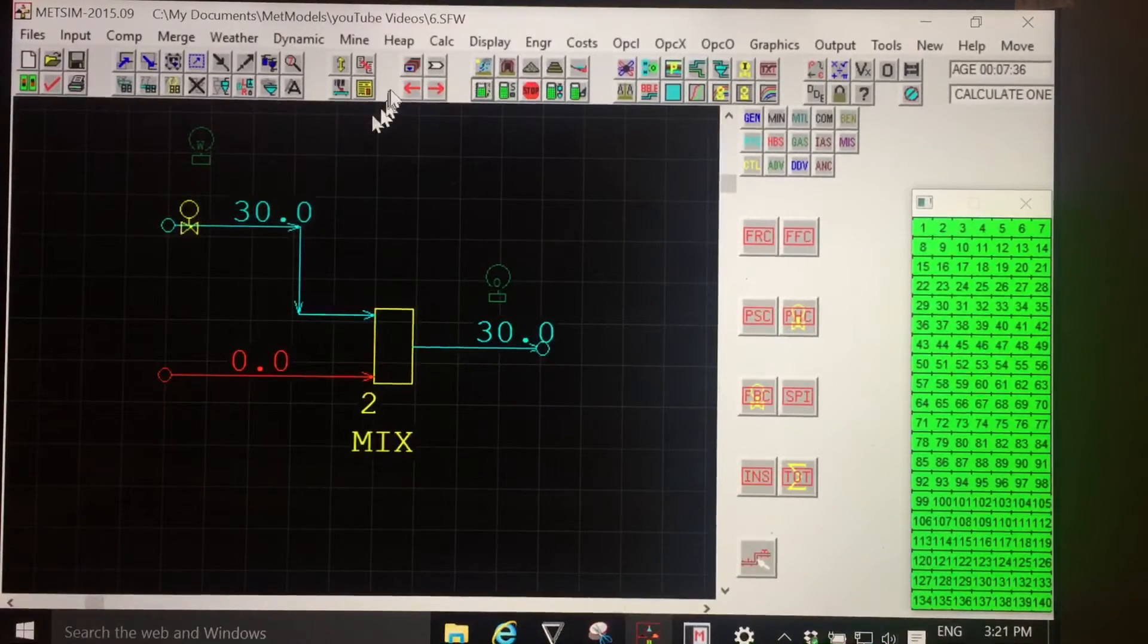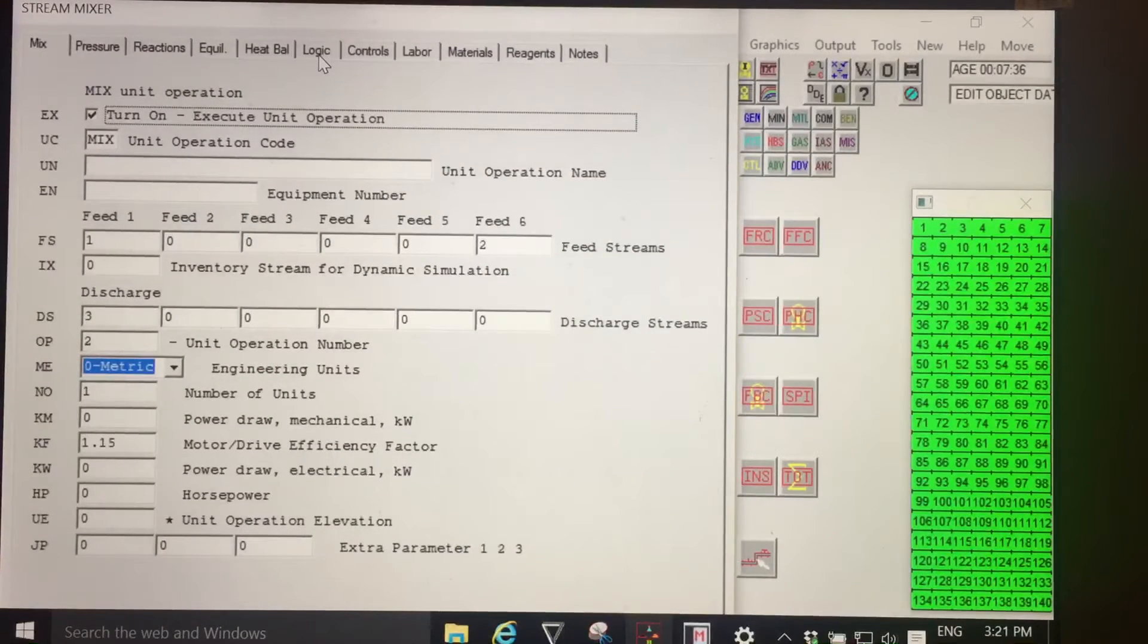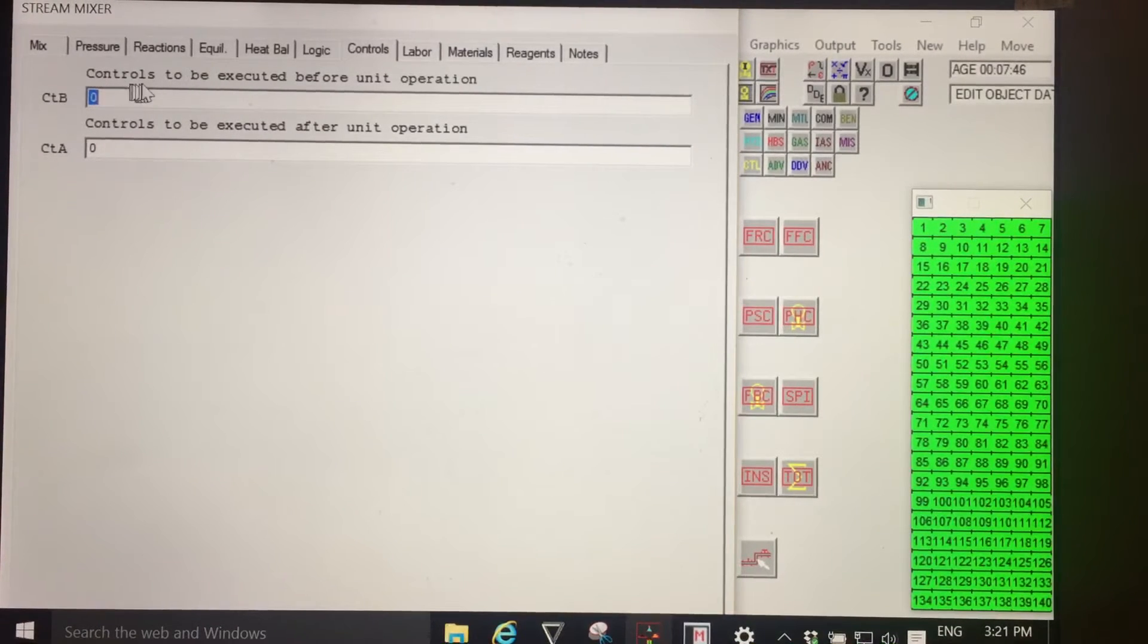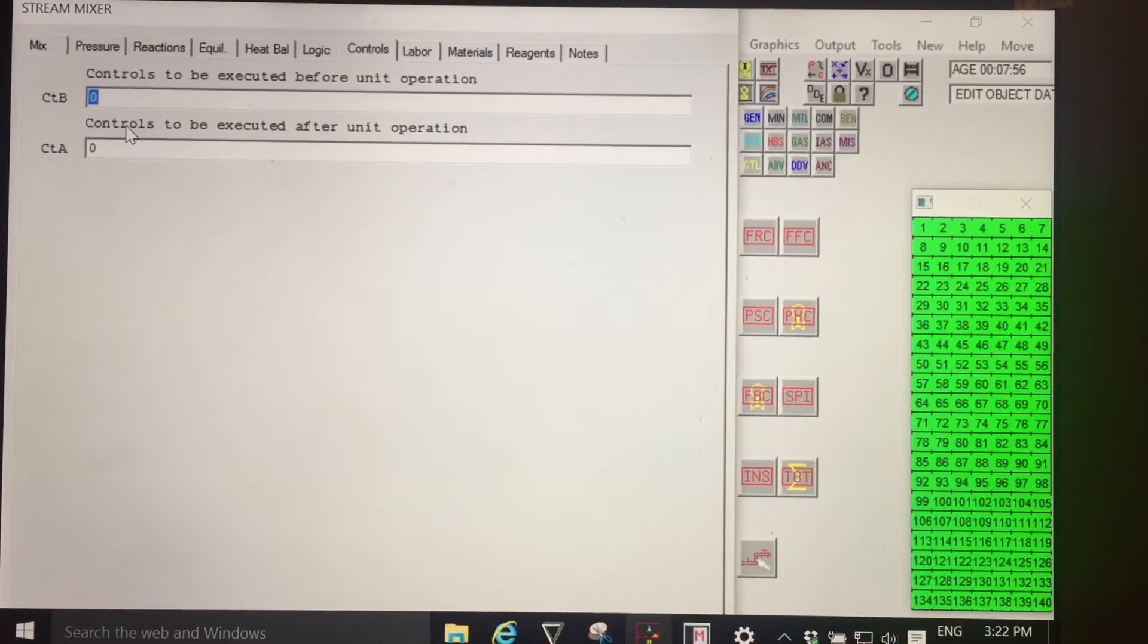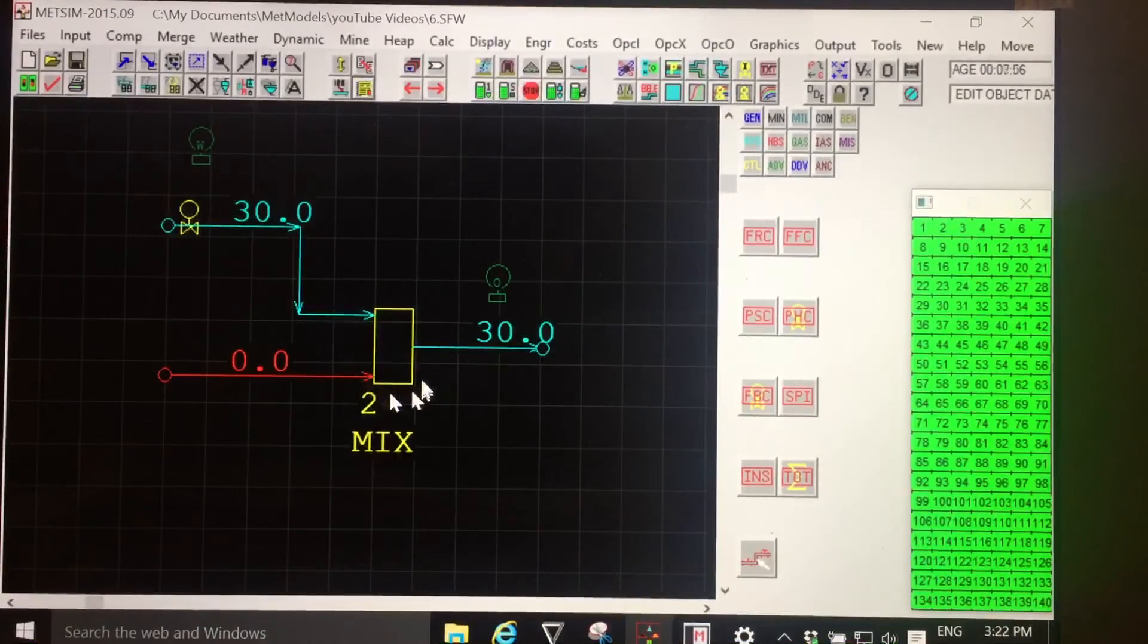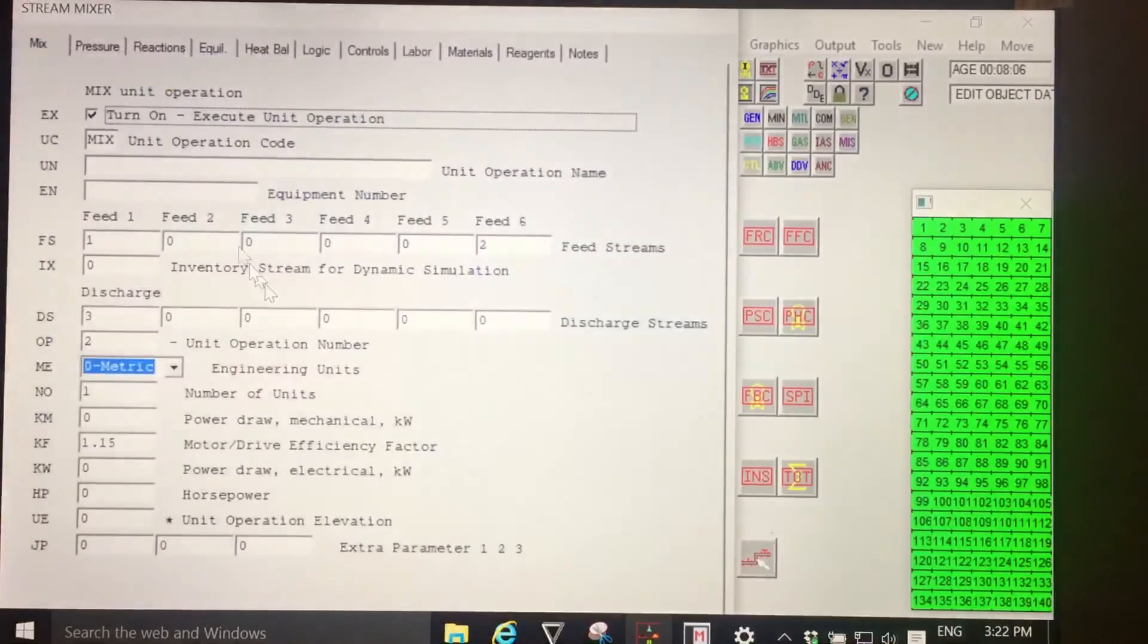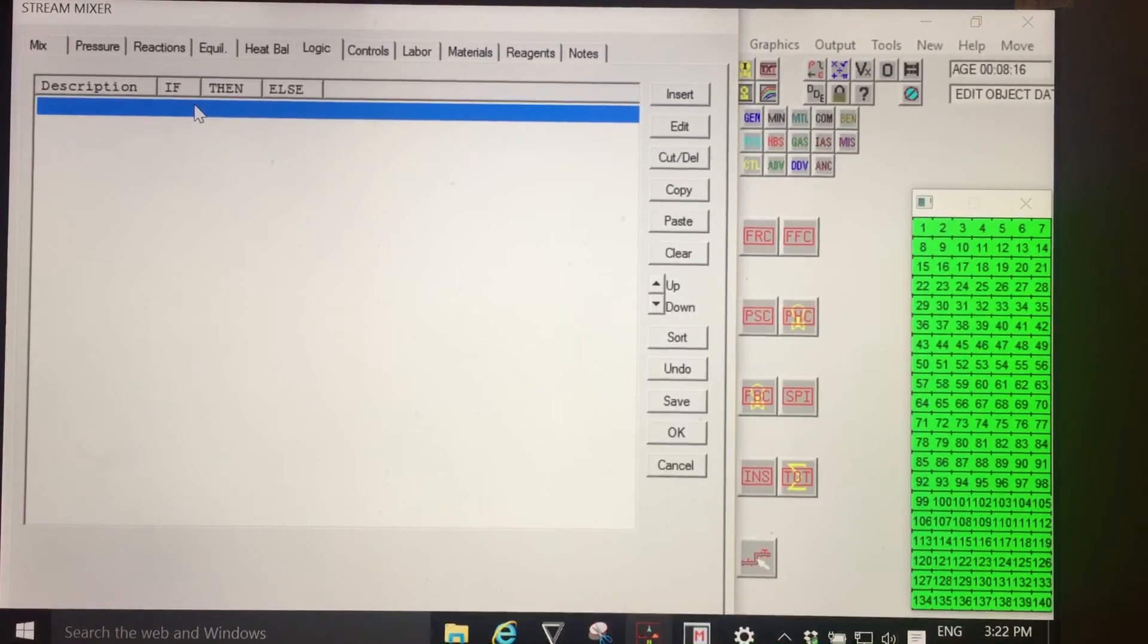There is another level of before, during, and after, and that is within the unit operation using controls, where we see CTB, which is a control or expression to be executed before a unit operation, and another CTA, which is a control to be executed after the unit operation. So there is another level of control sequence within a unit operation, and in fact we can take that further. We also have logic statements which are executed before the main program of the unit operation.